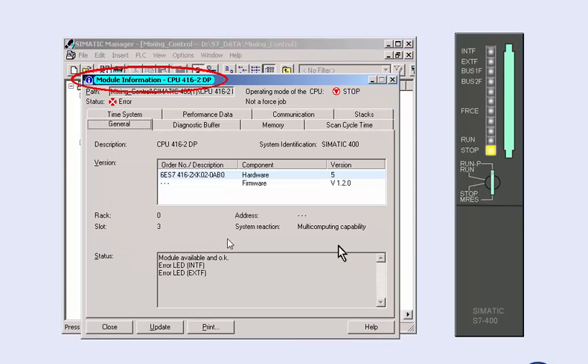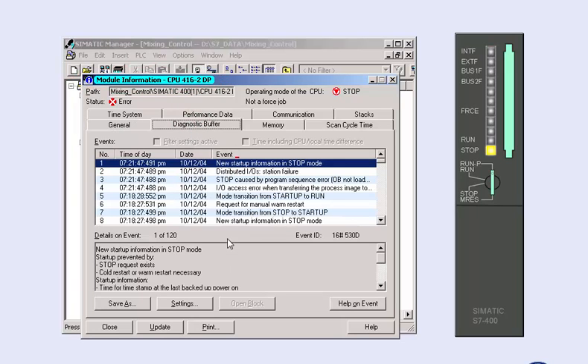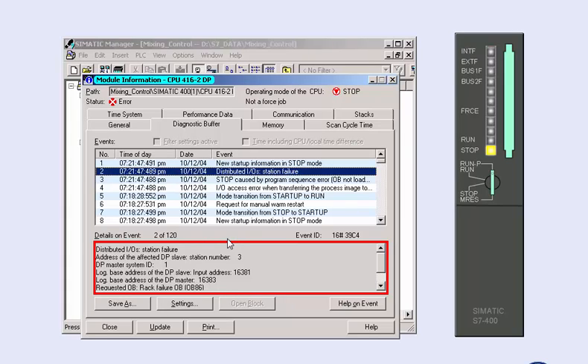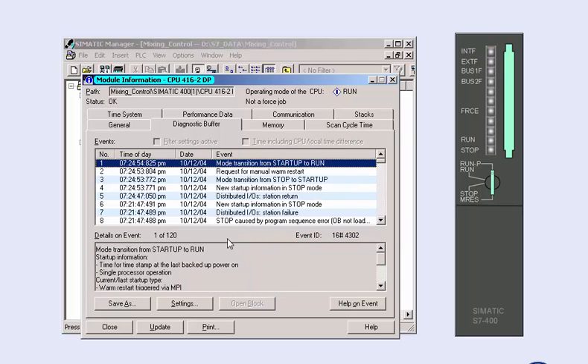In the displayed Information Status window of the CPU, you select the Diagnostic Buffer tab. The stop message is given at the top of the event list, and below you see the message with the error that caused the stop. In the lower window, the SIMATIC manager gives you further information on the error search as plain text. In our case, the diagnostics entry shows the failure of the PROFIBUS station number 3. The cause of the stop is removed by switching on the PROFIBUS station and restarting the CPU.